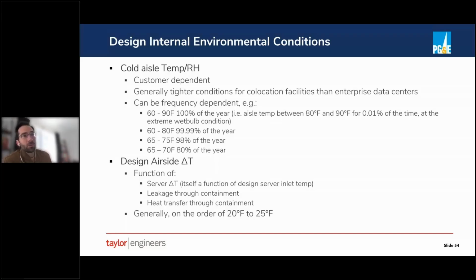And so in this example, if, for instance, we had a 20-degree delta T at servers, which is pretty low for modern equipment, maybe we should be designing our air handlers for 17 or 18 degrees. Most facilities these days, we're designing for between 20 and 25 on the air handler side. And that's simply because most servers will be higher than that. They'll be on the order of 30 degrees delta T at design conditions. But it doesn't necessarily make sense for most facilities to design based on the products that we're seeing today. It could very well be that the data center sees a large change over 10 years in the type of equipment used in that data center, and therefore our airside selections need to be flexible enough to accommodate changing IT equipment within the data hall.